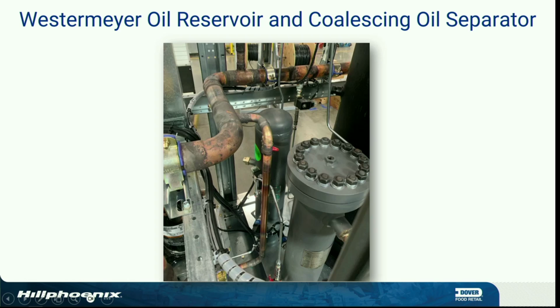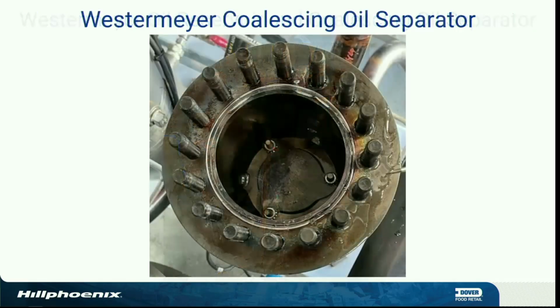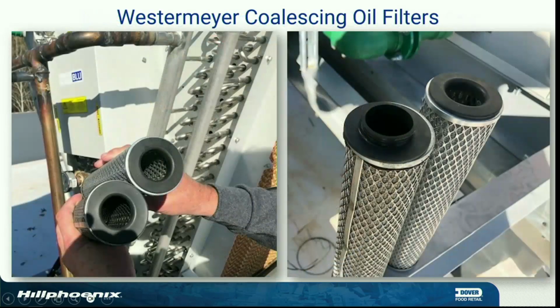All right? Me, I used to service Mycoms. Anybody familiar with Mycom compressors in the ammonia industry? Spring-loaded heads. So if you got a flood back of liquid, that head would literally lift off the plate and it would bypass and the head would reseat. Well, the trick to taking them apart is to take 2 bolts out, put 2 jacking screws in and bolts on them. Break all the other ones loose and then jack it out slowly, right? That way, when you hit it with a hammer and it's been stuck for a couple of years, it doesn't just bust off and take your face away with you.